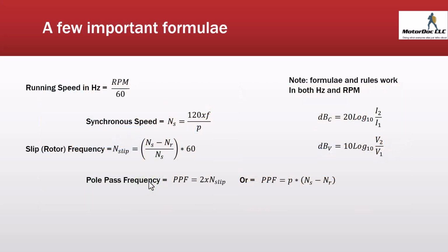A few important things to remember is running speed is the RPM in the nameplate divided by 60. Now that's full load speed. Synchronous speed goes up above that. So if I have a 60 hertz environment, now in a variable frequency drive, that changes, by the way, but 120 times 60 is 7,200. If it's a 4-pole, that would be 1,800. I come up here, and 1,800 divided by 60 would be 30 hertz. Now, the nameplate, of course, is not going to read that because a motor cannot run at synchronous speed. So it's going to be some value close to that, say 29.7 hertz, that kind of thing, and will vary a little bit based on load.